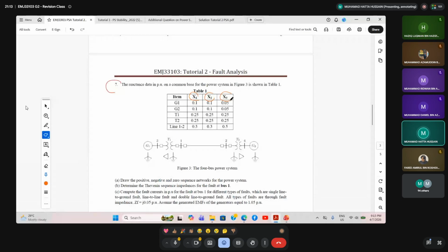But for the zero sequence, we have totally different values for generator 1, generator 2, and the transmission line going to transformer 2, except that transformer 1 and transformer 2 have the same zero sequence reactance value, similar to the positive and negative sequence reactance.